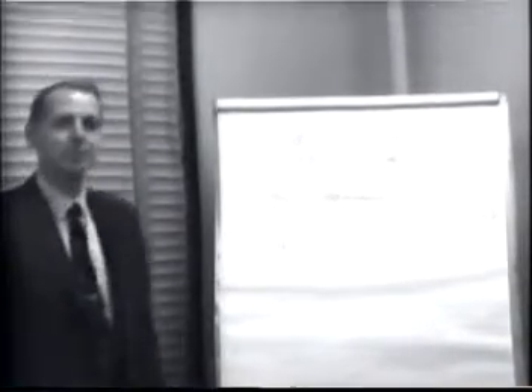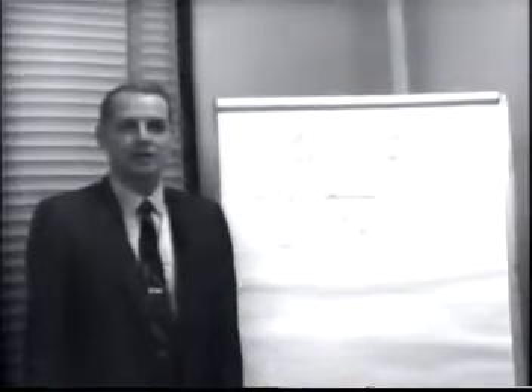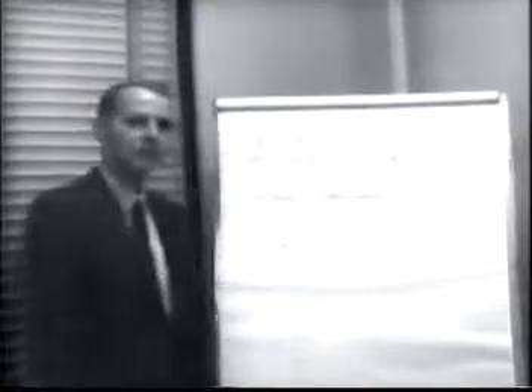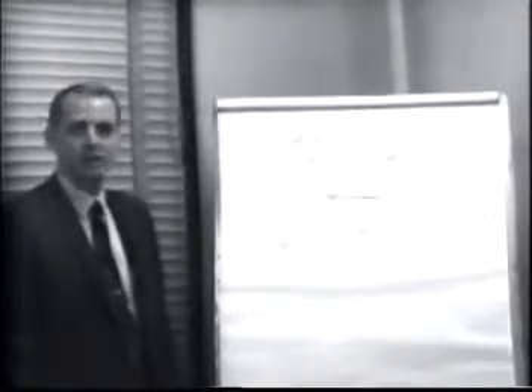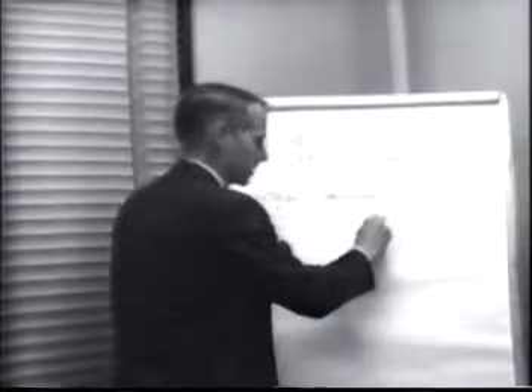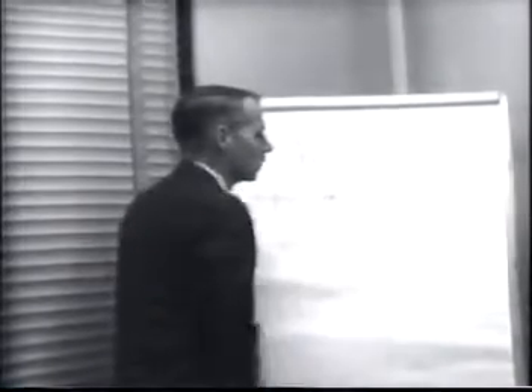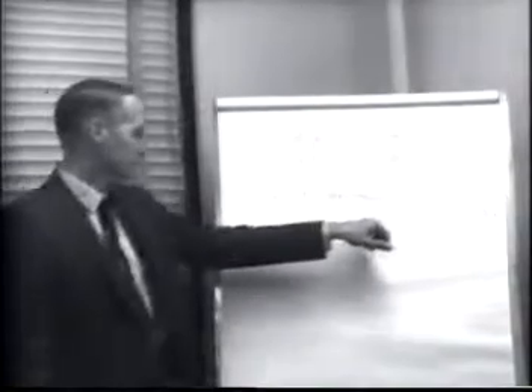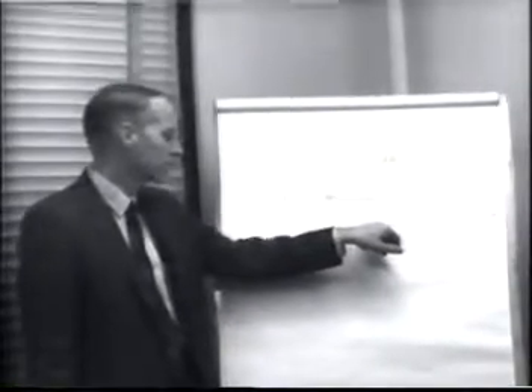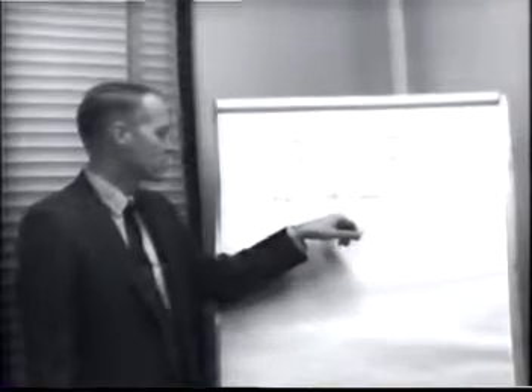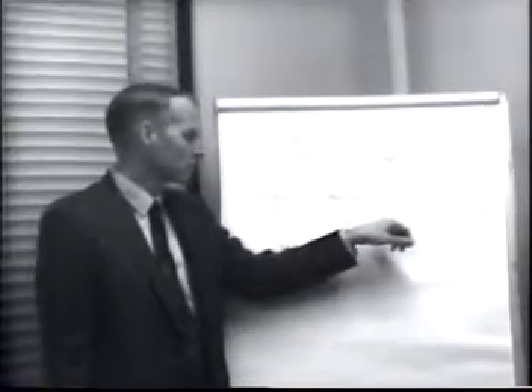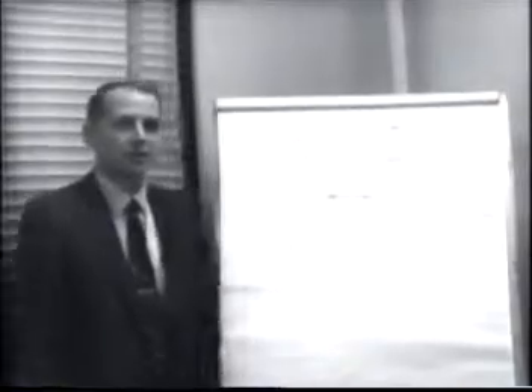If we have a line between two numbered subs, in general they're placed in numerical order. Say we had a 13 kV line from sub 20 to sub 22. That would be 20, 22, 1. We use the hyphens to distinguish between the voltage level and the substation, and between numbered subs, and between numbered subs and the number of lines between a given 2 points. Hyphen is not used between two lettered subs. Now let's show a few examples of this.